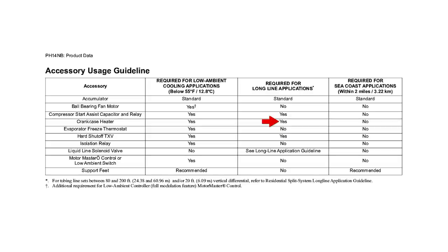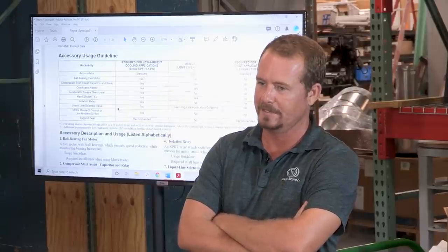Crankcase heater, yes. Why do we have a crankcase heater in a long line application? First off, what's the purpose of a crankcase heater? What does it do? Let's just start with breaking the name of it down. It heats the crankcase. But why do we want to heat the crankcase? If there's liquid that is sitting inside the compressor, the heat will help boil it off before startup. Well, it'll prevent it from going there in the first place. It'll prevent it from condensing in the first place.